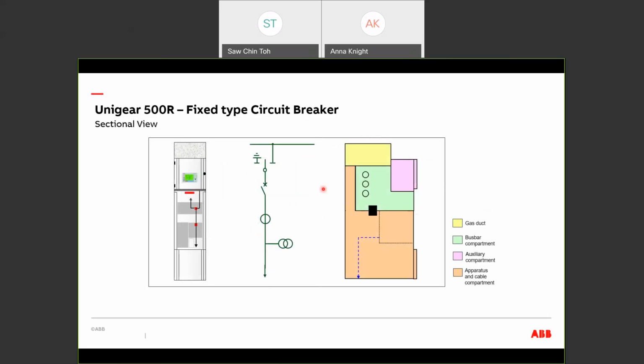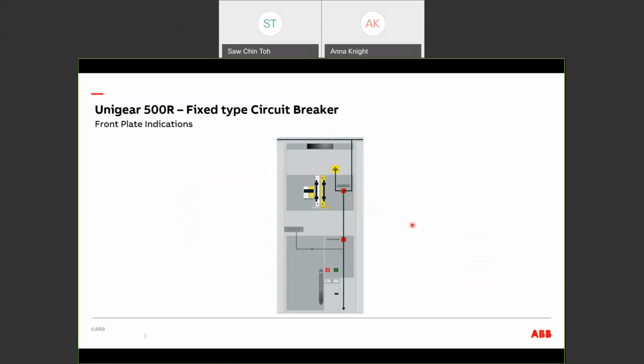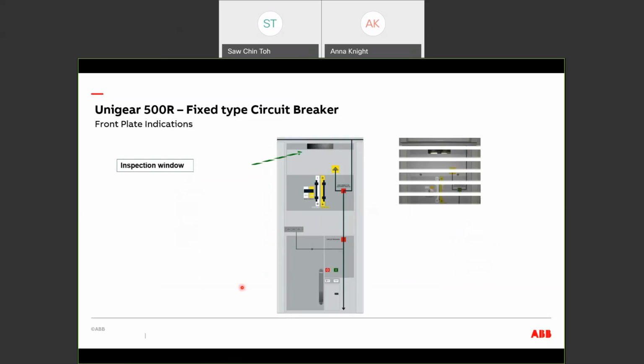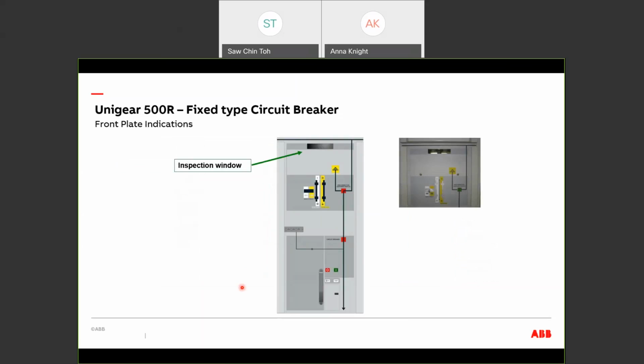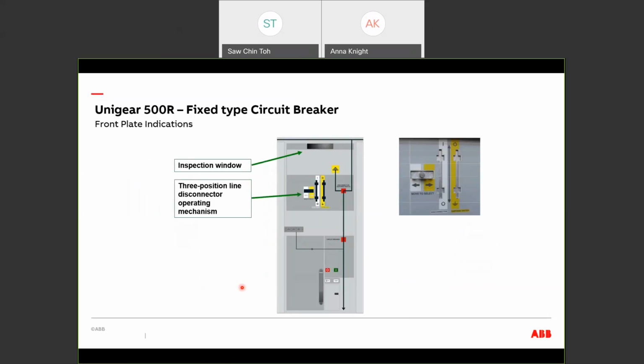This is the typical sectional view of the UniGear 500R. It has 2 main compartments: the bus bar compartment at the top, and the combined circuit breaker and cable compartment at the bottom. The arc duct runs at the top, and then this is the LV compartment. The operation of the panels is done through the front of the cubicle. We have a viewing window to view the position of the 3-position switch, and these are the slots for operating it. The handle is provided with the switchgear for you to operate the 3-position switch from the closed position to the isolated position, and also from the isolated position to the earth position.